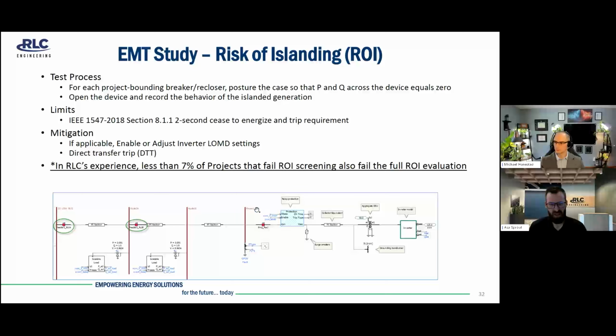And just to give you a quick picture of what we'd actually be simulating here. So on the right is the same exact project model I showed a few slides ago. On the left, you have 2 reclosers that are circled in green. So this first one here is the feeder recloser that is responsible for providing protection to the entire feeder. So we would get the P&Q flows as close to 0 as possible here, trip it, and then see how the project performs. And then we would repeat that exercise for this downstream line recloser.